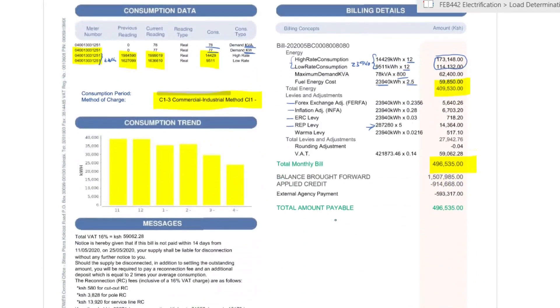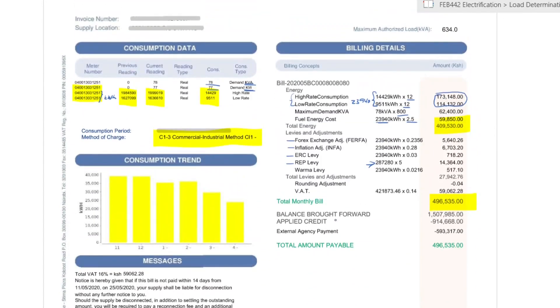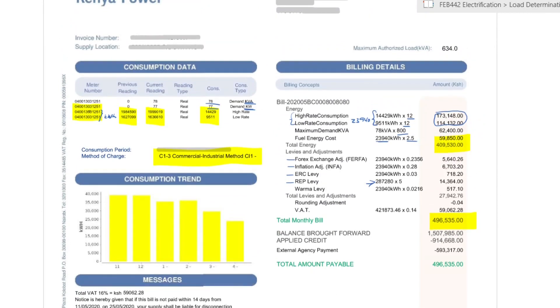This billing structure applies across the board whether it is commercial, industrial, or domestic — the only difference is the tariffs encountered. In a domestic case, for example, there is no maximum demand kVA charge, as domestic customers are excused from that. Additionally, the ratio between kVA and kilowatts is used to determine the power factor. If that ratio falls below a certain amount, there will be a penalty charge for poor power factor — in this particular case there is none, but the possibility exists if power factor correction is not implemented.